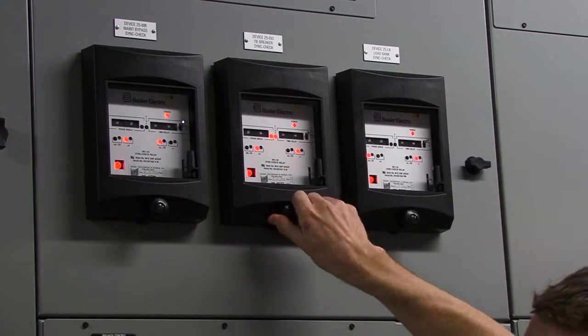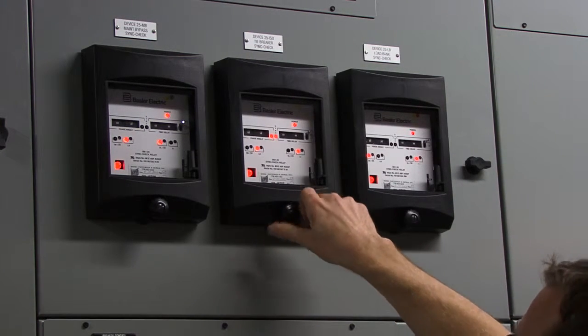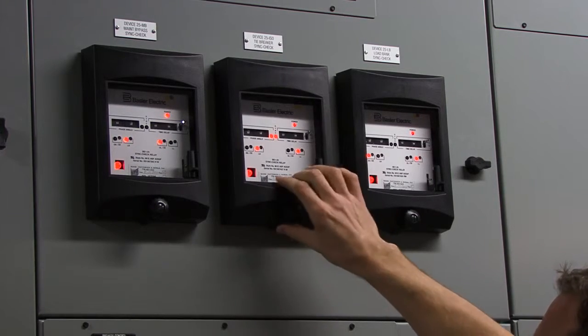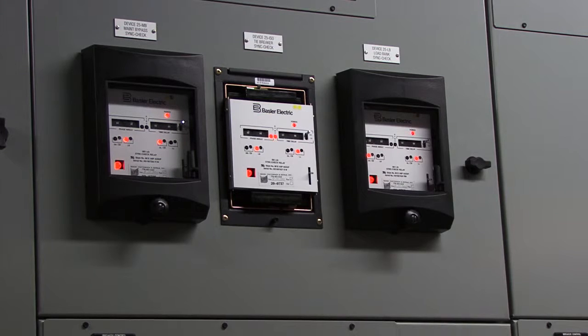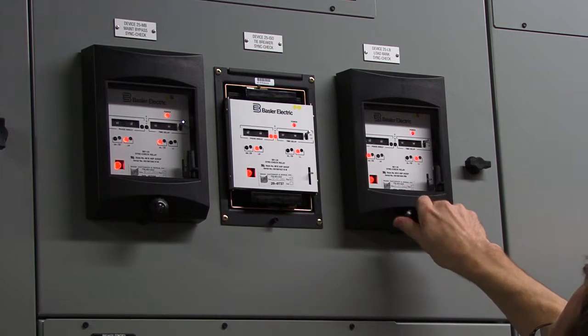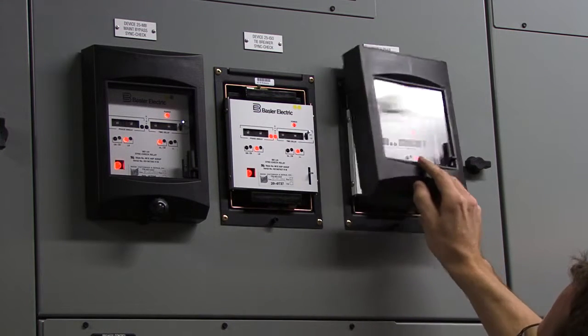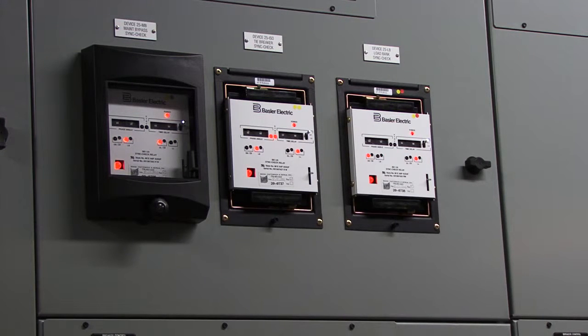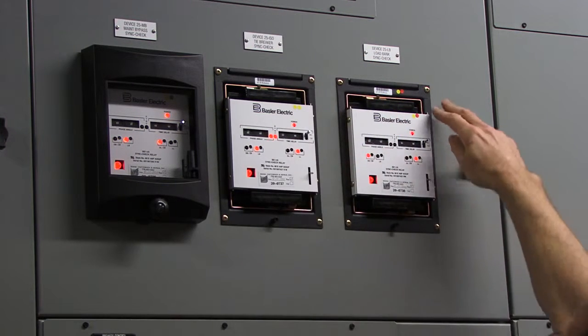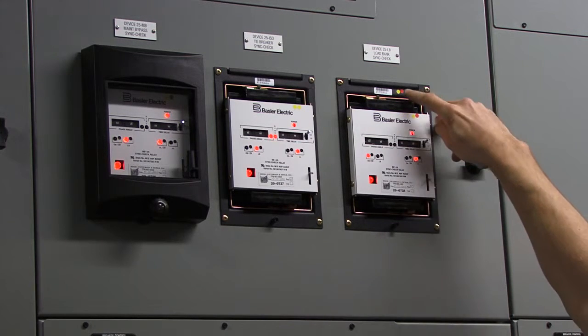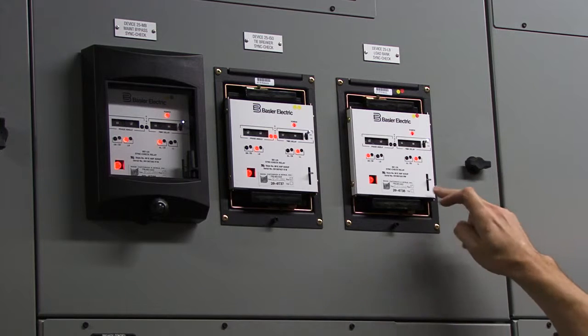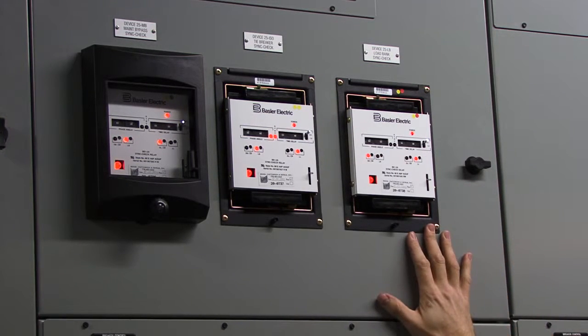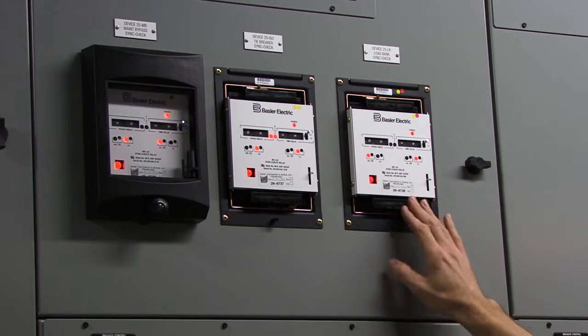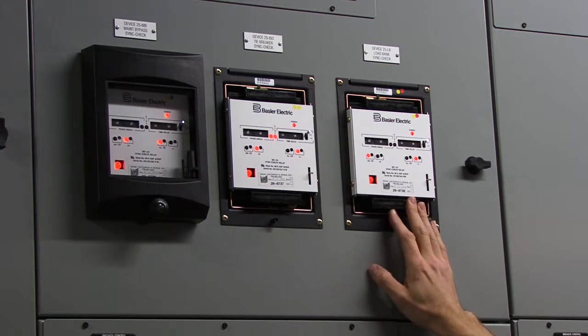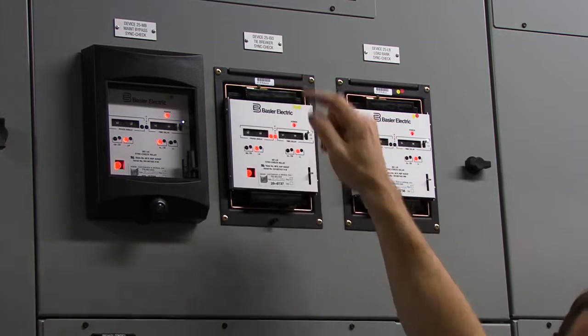And I meant to mention this at the UPS input substation. We've color-coded the relays. Must have fallen off. I guess the stickers must have come off right there, but if you look here, there's a yellow dot, and a red dot, and a red dot, and that's just to tell you that this relay is associated with this location in the board. And since these aren't set the same, it's important that this relay goes back where you got it from. Same thing for here. I'll add some yellow dots up there. They should be there. They're not.